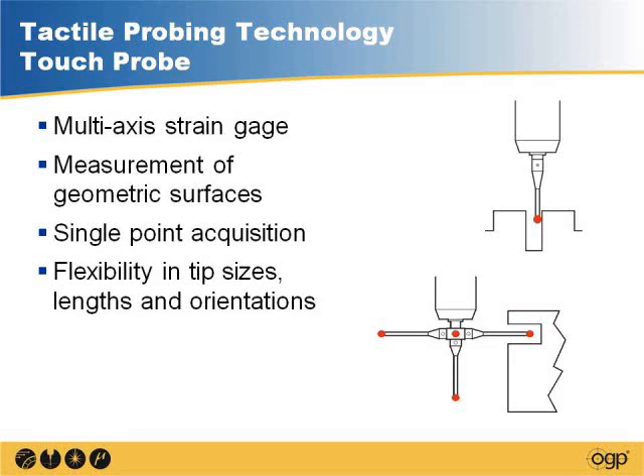What this uses typically is a strain gauge technology, where when that probe is triggered, it senses that point, takes the XYZ data point, and then you can create different geometries and information from that. It does single point acquisition, so you're moving this XYZ stage on a measurement system, and the probe is actually contacting the part one point at a time. It's good for measuring geometric surfaces. Like I said before, video is used to measure edges where surfaces intersect, and this is more for measuring surfaces like cylinders, planes, and things like that.